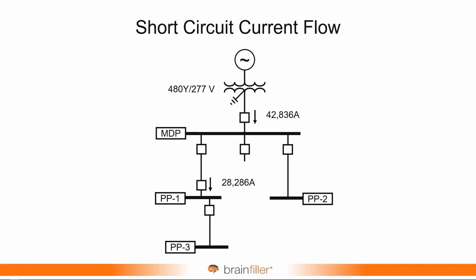And the available fault current is going to be different at each equipment location. This is part of what drives the incident energy calculations in an arc flash study. You have the clearing time, how long it takes a device to operate, but you also have the magnitude of fault current that goes into this.